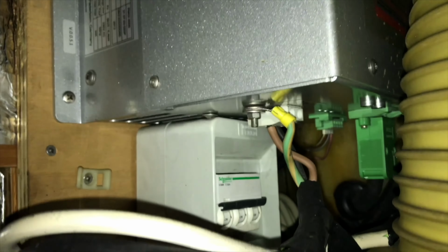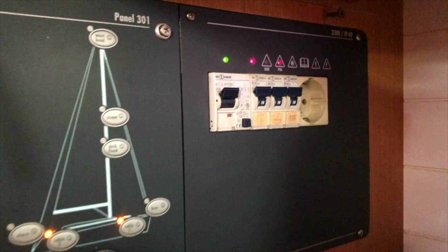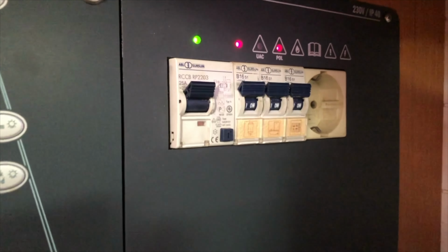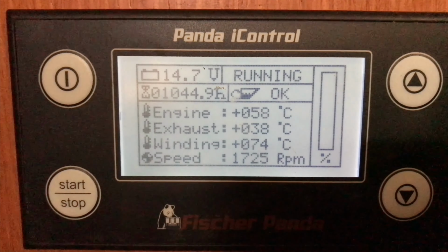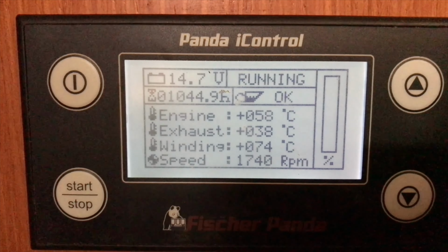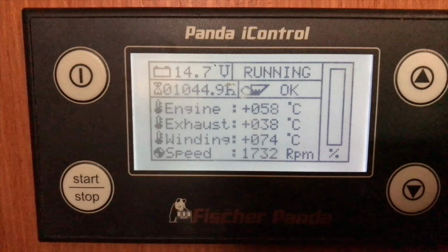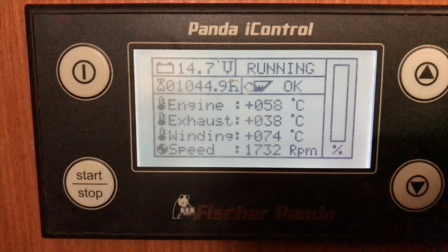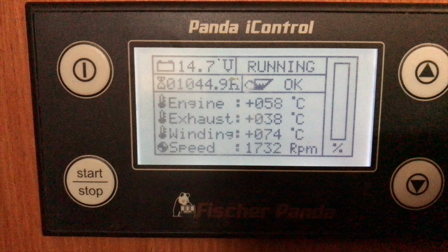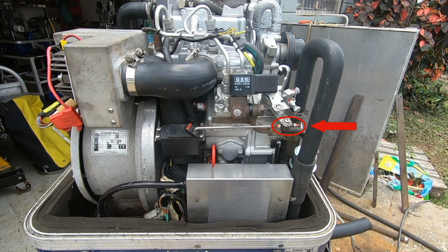Because one of the things that seems to work pretty well with the Panda is actually the inverter part. However, I have experienced that it does not kick in and is not delivering any 220 power. After checking all the fuses and switches, I more or less accidentally discovered the RPM was too low. On the 8000, it needs to be above 1700 RPMs to deliver power. So a tiny adjustment on the throttle solved this problem.